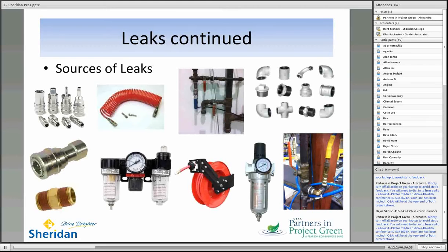So, if I've convinced you that we want to be looking at leaks, where are we going to find them? Well, here are some of the usual suspects: couplings, fittings, pipe joints, any spot where I've got a junction, where I've put some pipe thread and wrapped it in Teflon tape. Hopefully I've put some Loctite or something on there to really seal that. But often we find those 1/32-inch and 1/64-inch kind of leaks around those kinds of things.